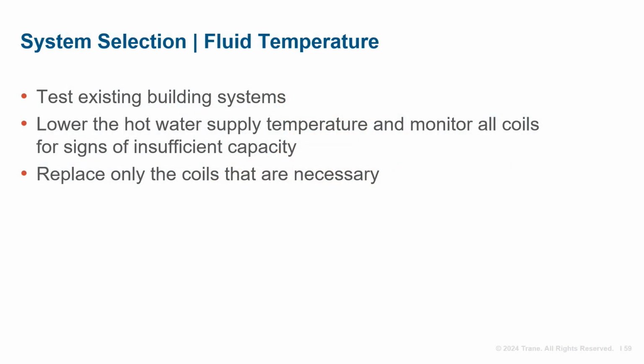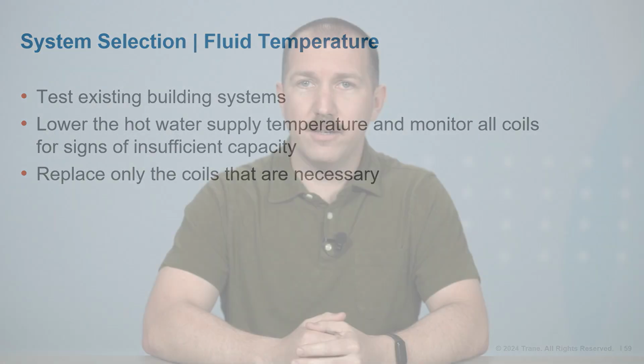If the domestic hot water system is tied into the building heating hot water system, it's often best to separate it. This allows the building hot water supply temperature to drop below that required by the domestic hot water system. Remember that not every coil in the system needs to be replaced. In order to supply the building with lower hot water temperatures, identifying and selectively replacing only the coils that failed to provide sufficient heating capacity during testing or modeling helps keep the project scope, and therefore cost, at a more manageable level.